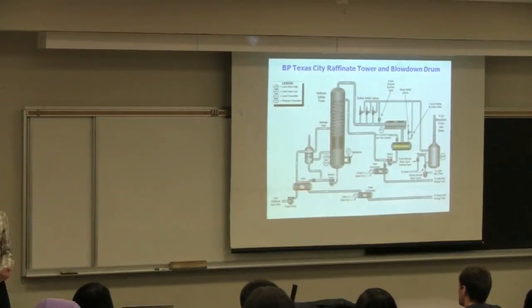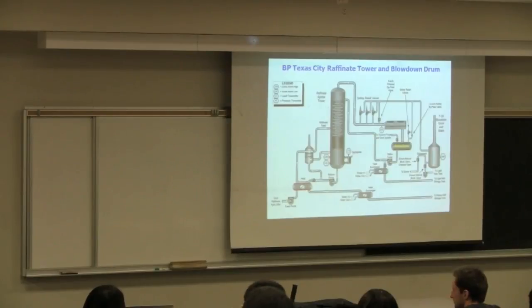We often find, counterintuitively, that for steady state operation, for good regular operation, heat integration works really well, it saves us money, but it's hard to get past that safely during a startup mode. You have to think really, really carefully how you're going to start up when you have an integrated energy system to prevent issues like that. So this is going to come up in the hazard and operability studies that we look at. Great to have energy integration and these cost savings, but how do you start up the process safely to avoid any bad events happening?